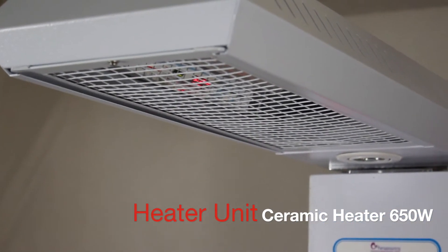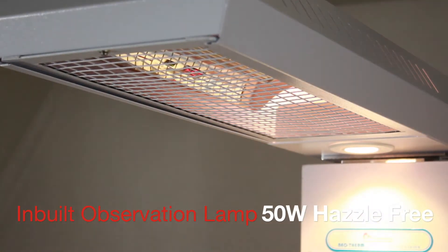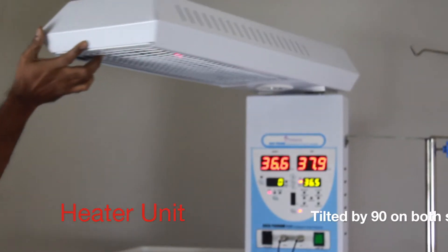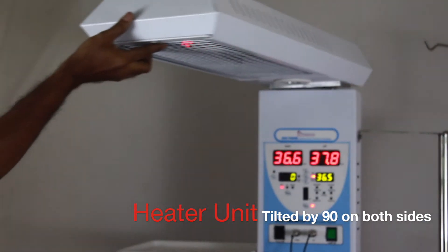The heater unit comes with a 650 Watt ceramic heater with parabolic reflector. The inbuilt observation lamp is a 50 Watt bright, hassle-free lamp whose angle can be set easily. The heater unit can be swiveled on both sides to facilitate proper X-ray measurement.